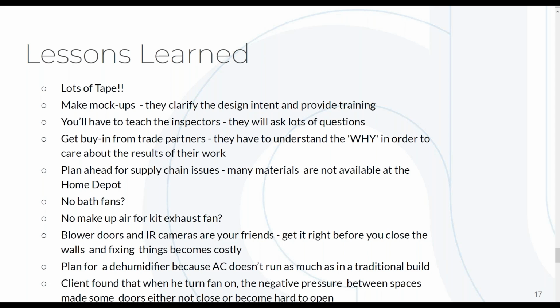We have no bath fans on this project. That was a fun conversation with our inspectors. They didn't understand why we didn't have bath fans, and we had to make sure that they understood that we have ERVs, and we're pulling air out of our bathrooms and out to the outside and replacing it with new fresh air that's been filtered and conditioned. And we also have controls in place that we could hit a boost button. So that ERV runs all the time, but if we know we're in the bathroom and we're creating moisture that we want to pull out, we could kick that up and make sure it's going to have a little bit more boost to it for those times. So there's ways around having no bath fans, and that was one of the conversations that had to be had.